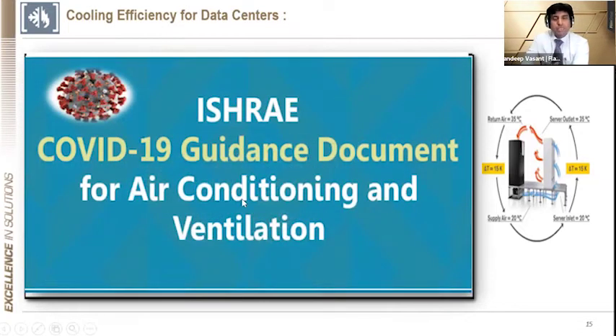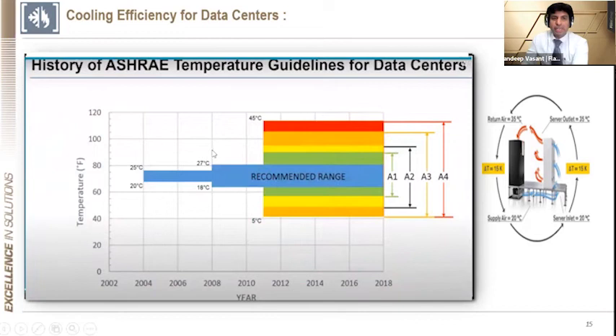Now, apart from the ASHRAE document, there is also an ISHRAE guideline which talks about impeding the COVID virus, and the temperature gradients are very much in line with ASHRAE, that is between 24 to 30 and 40 to 70% RH. So thereby it is in line with the ISHRAE guidelines for COVID. So this is to give you a history of the ASHRAE document.